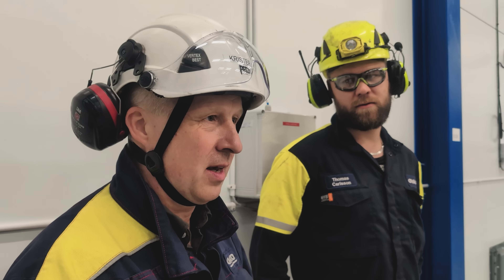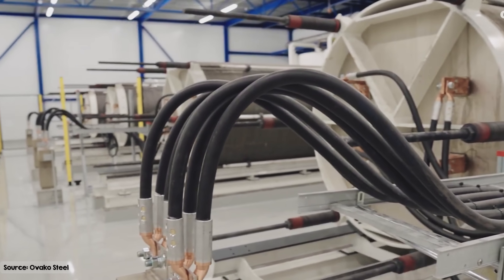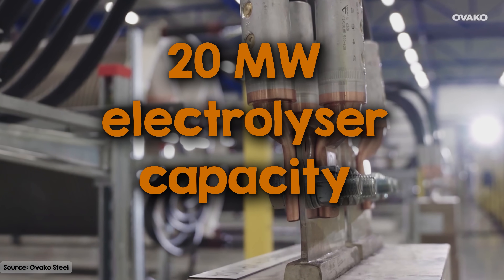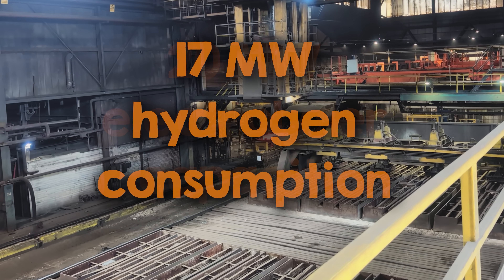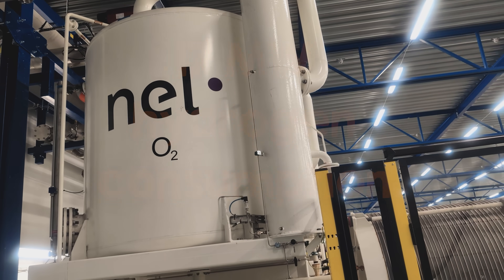These are the electrolyzers — eight stacks of electrolyzers. This is 20 megawatts of hydrogen production. The reheating furnaces, running at full speed, use about 17 megawatts, so we have a few megawatts to spare. We use the hydrogen for heating, and also the oxygen — putting it on our distribution system to be used in different furnaces. We also use the excess heat from the electrolyzer to feed the district heating system, heating up some villages around the area.